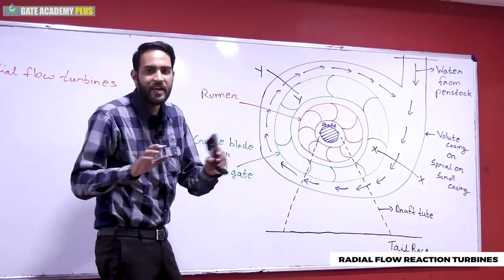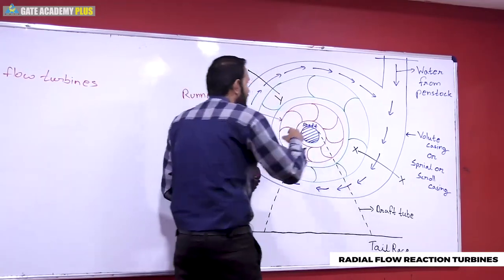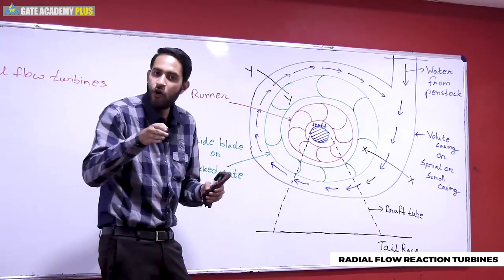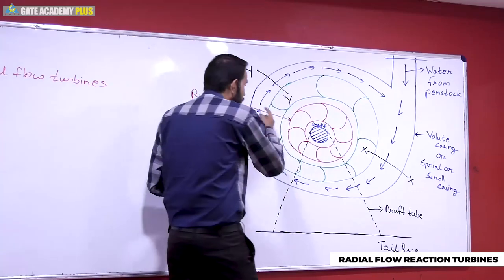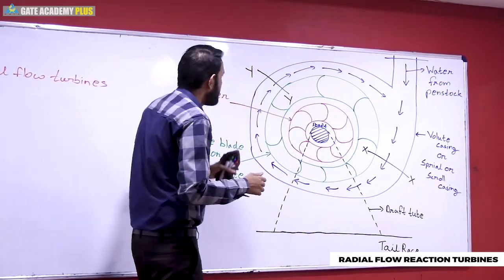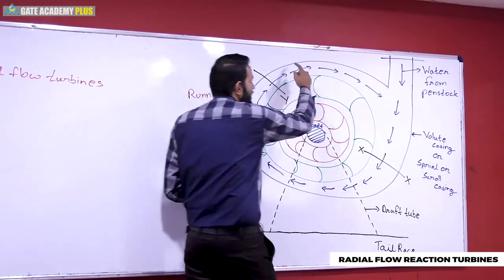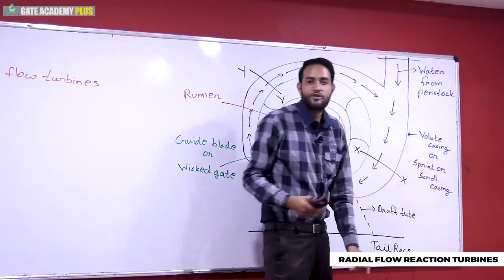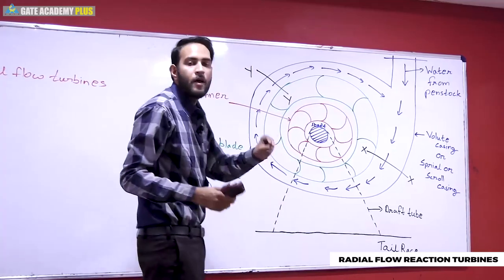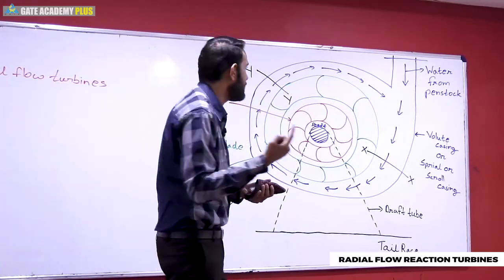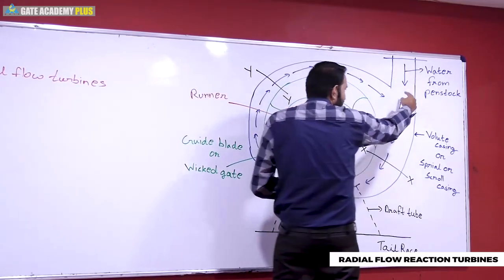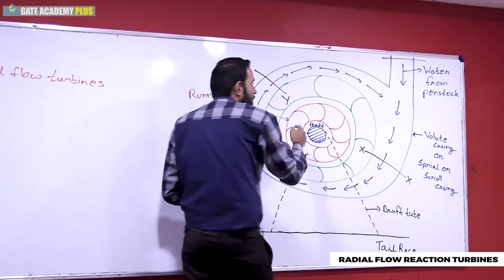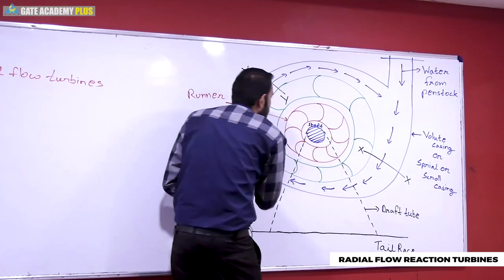The guide blades are fixed and the runner rotates. The flow is guided through the blades for shockless entry into the runner. This is our turbine casing — it is called a volute casing, spiral casing, or scroll casing. You can see it has a spiral shape. Water enters from the penstock and is distributed around the whole periphery. The guide blade acts like a nozzle, increases velocity, and water enters for shockless entry and rotates the runner.